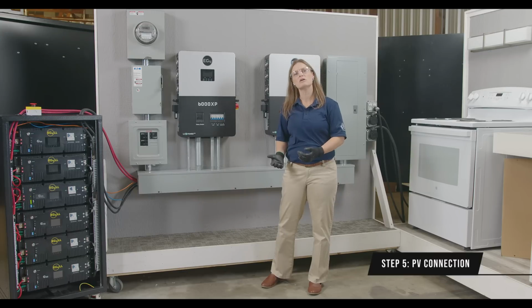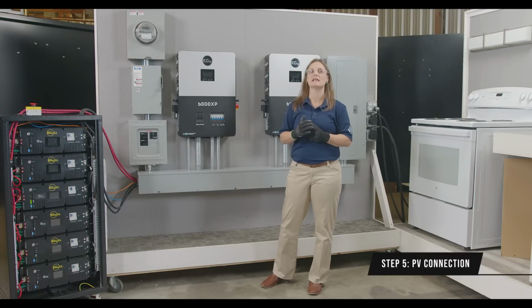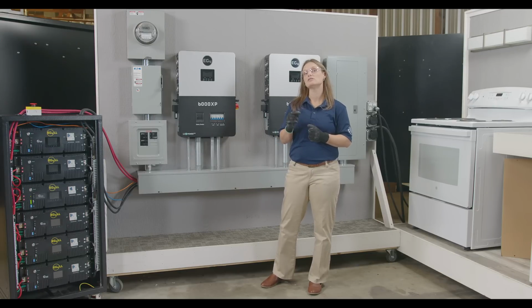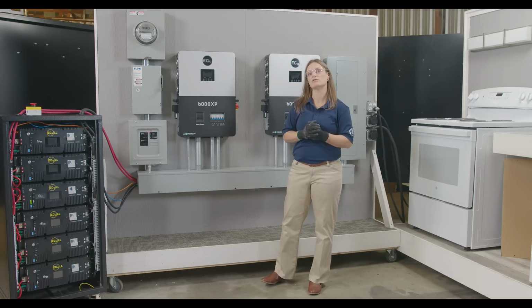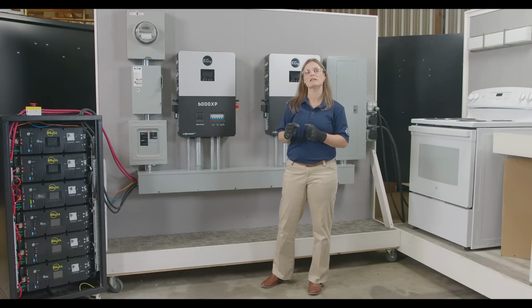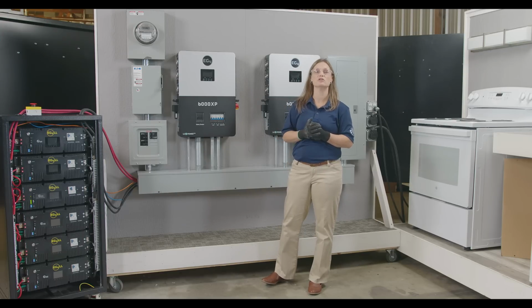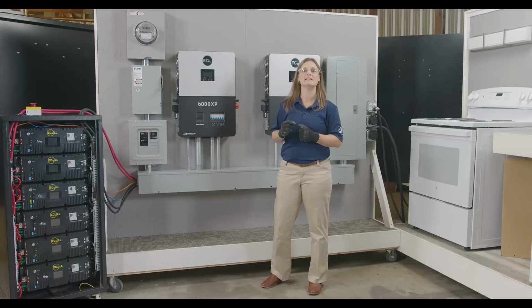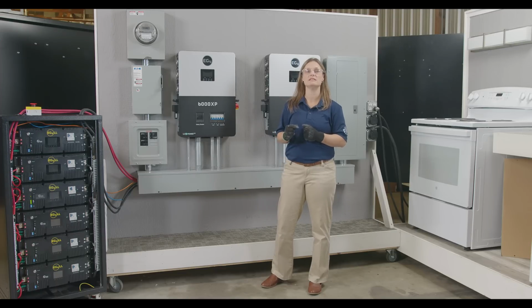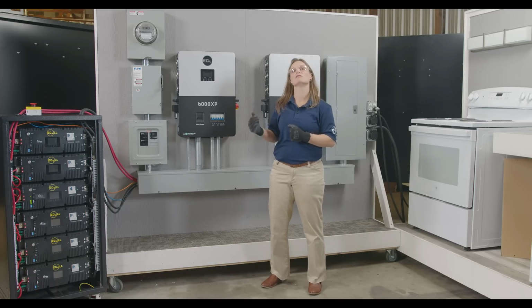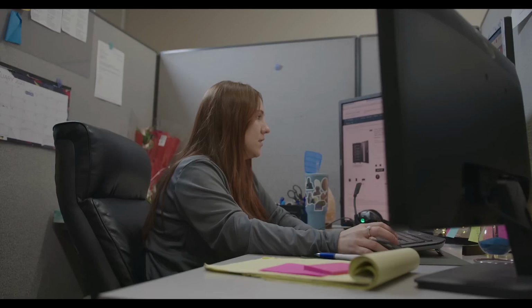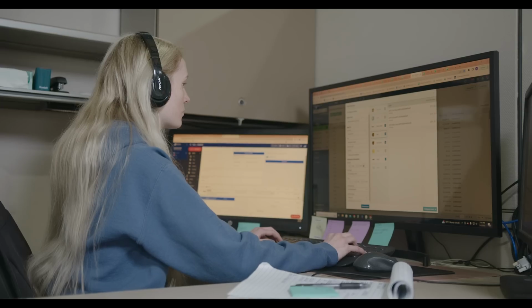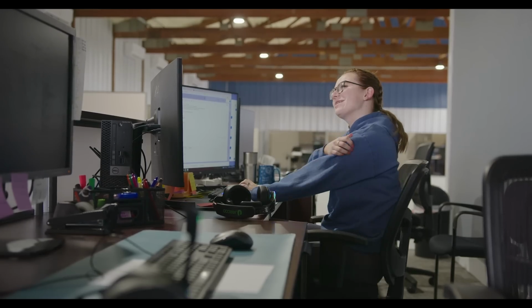Factors like voltage drop and cold weather need to be considered since these can push the voltage above the inverter's 480 volt DC limit. Also, double check your string size of your PV arrays, keeping in mind the lowest temperature possible for your area. The inverter needs at least 140 volt DC to start and shouldn't go over 480 volt DC. For guidance, reach out to our sales, design, or tech support teams here at Signature Solar.